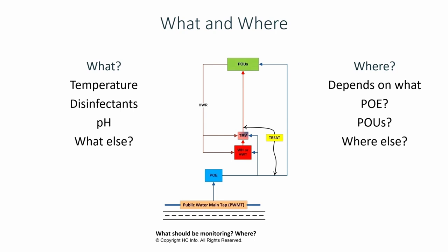Besides points of entry and points of use, where else? For temperatures, for example, where might you also test? Hot water return? Yeah — water heater outlet, or mixing valve outlet. Back to those medical tests: you could think about temperature, disinfectants, pH, and probably flow as analogous to monitoring exercise and diet for cholesterol. If you get off your diet for a day or skip a workout, it's not like death is around the corner. It's something that over time and cumulatively can affect the cholesterol results. That's how you would look at temperatures, disinfectants, pH, and flow.